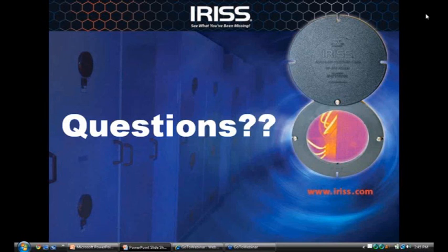Excellent. How about, here's another one for you, Martin. Does IR work with fiber optics for those switchgear cubicles having internal covers? No. But there are a number of options. I know you talk about metal clad gear when you've got stab connectors or electrical connections behind internal cladding inside the switch. There's a number of modifications we've done with switchgear companies. We use standard heat transference techniques and things like that. Anytime, drop me an email, I can give you more information on that. And 10 Things You Need to Know About IR Windows covers that subject in a little bit more detail.